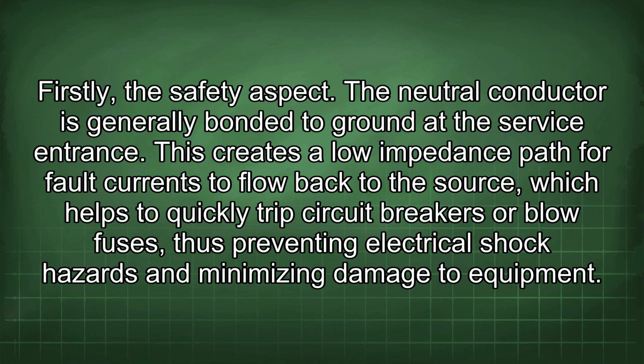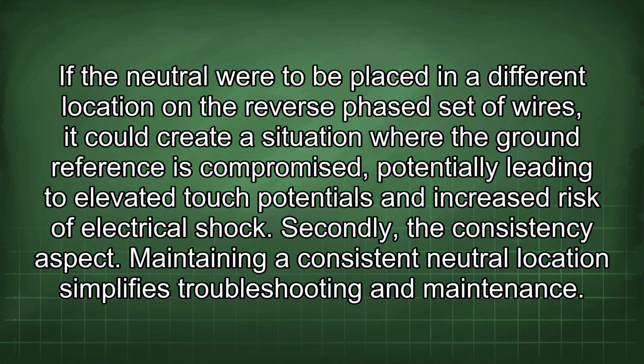The neutral conductor is generally bonded to ground at the service entrance. This creates a low impedance path for fault currents to flow back to the source, which helps to quickly trip circuit breakers or blow fuses, thus preventing electrical shock hazards and minimizing damage to equipment. If the neutral were to be placed in a different location on the reverse phase set of wires, it could create a situation where the ground reference is compromised, potentially leading to elevated touch potentials and increased risk of electrical shock.